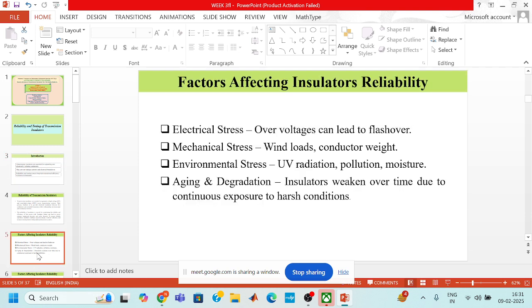There are some factors which affect the insulator's reliability. These are electrical stress, mechanical stress, environmental stress, and aging and degradation. Due to electrical stress, overvoltages can occur, which lead to flashover. Wind loads and conductor weight cause mechanical stress. UV radiation, pollution, and moisture come from environmental stress. And due to aging and degradation, insulators weaken over time due to continuous exposure to harsh environments.